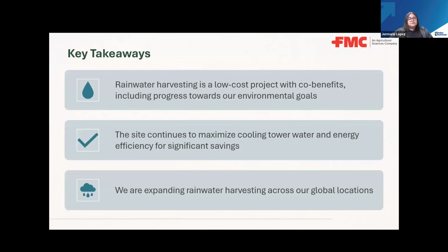So rainwater harvesting is a cost-effective initiative that not only provides economic benefit, but also supports our broader environmental goals. This project helps reduce water consumption and chemical treatment costs while minimizing environmental impacts such as reliance on groundwater and the loads that we send to the wastewater treatment plant. In addition, the site has successfully optimized the cooling tower and energy efficiency, leading to significant savings. By using rainwater for makeup water, the cooling system operates more sustainably, with reduced blowdown, lower chemical use, and decreased evaporation, all contributing to both efficiency and cost reduction.